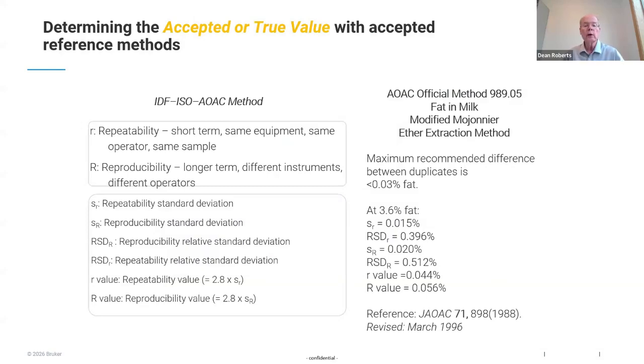All right, so looking at the repeatability and the accuracy of the near-infrared, I wanted to throw up the accuracy here for the Mojonnier method for doing milk fat. And these are developed by round-robin studies, taking a number of laboratories, throwing out the low, throwing out the high, and then looking at the average values from each one of the laboratories. These are the methods that exist for fat, for protein, for total solids, for lactose, and these are the basis for all calibrations of near-infrared spectrometers, FT-NIR spectrometers, Raman, or any other technologies that are used for measuring dairy products.